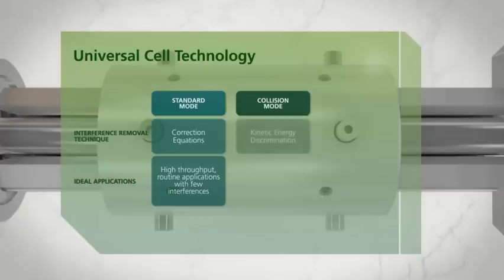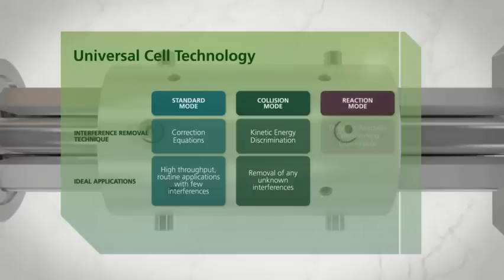Use collision mode with kinetic energy discrimination for the easiest setup and the analysis of environmental samples or the testing of unknown samples using a single gas. Or quickly switch to dynamic reaction mode for any analysis requiring the best detection limits.